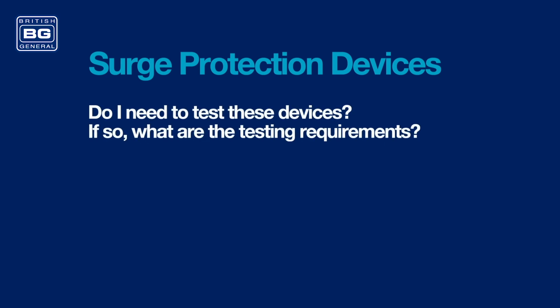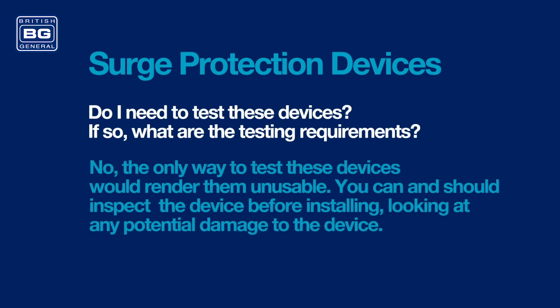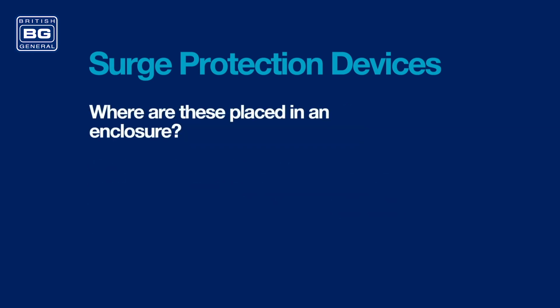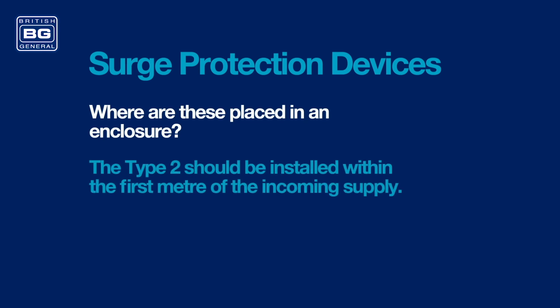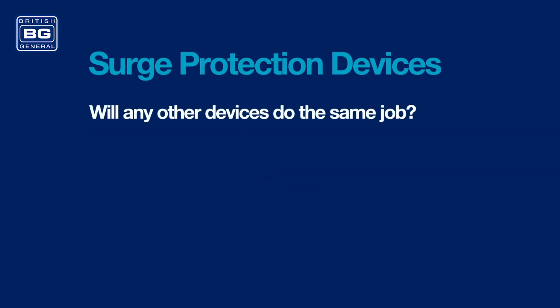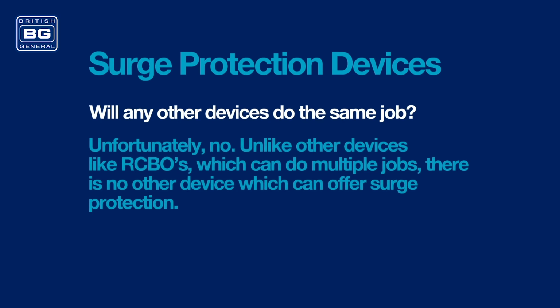Do I need to test these devices? If so, what are the testing requirements? No, the only way to test these devices would render them unusable. You can and should inspect the device before installing, looking at any potential damage to the device. Where are these placed in an enclosure? The Type 2 should be installed within the first meter of the incoming supply. Will any other devices do the same job? Unfortunately, no. Unlike other devices like RCBOs, which can do multiple jobs, there is no other device which can offer surge protection. Here are a few frequently asked questions concerning electric vehicle charging.